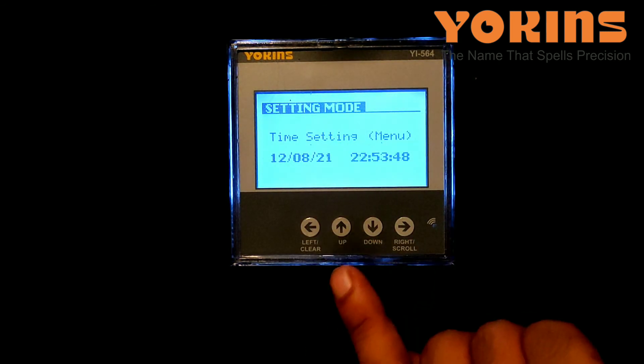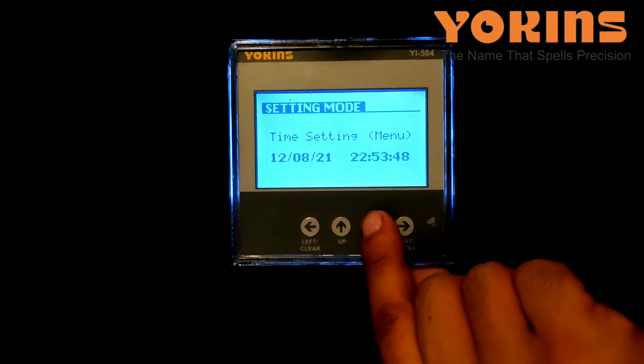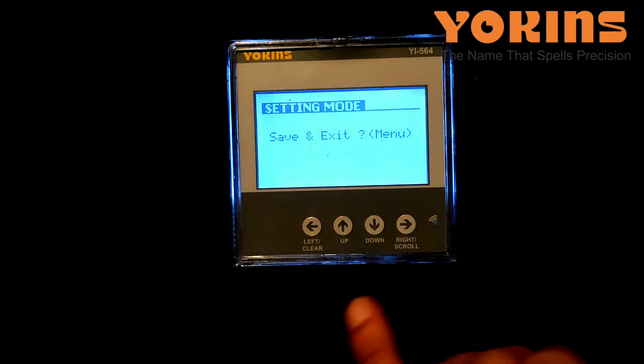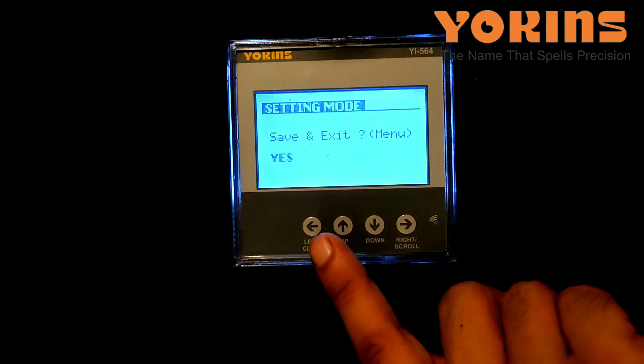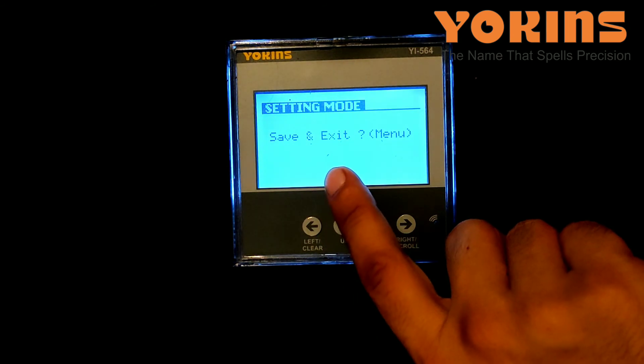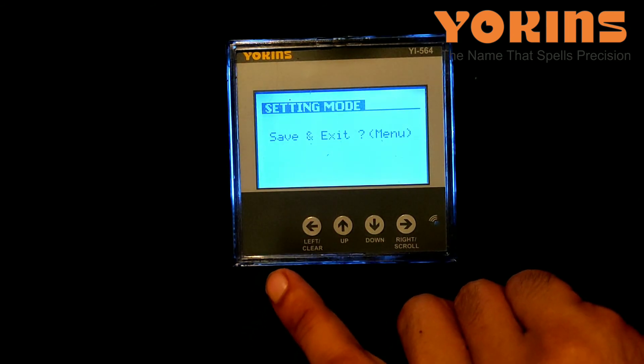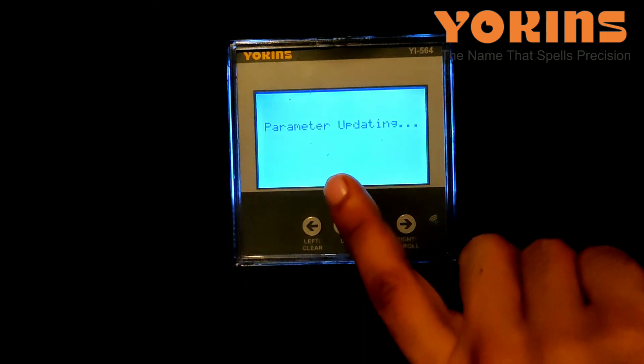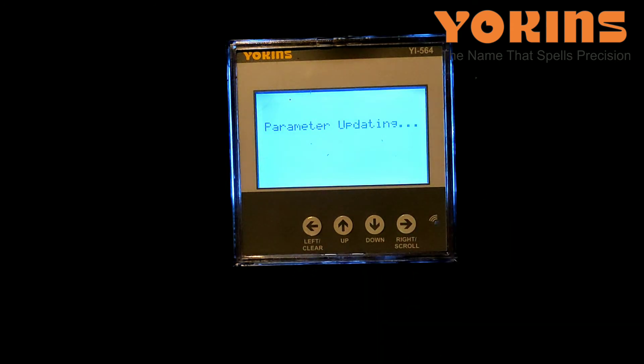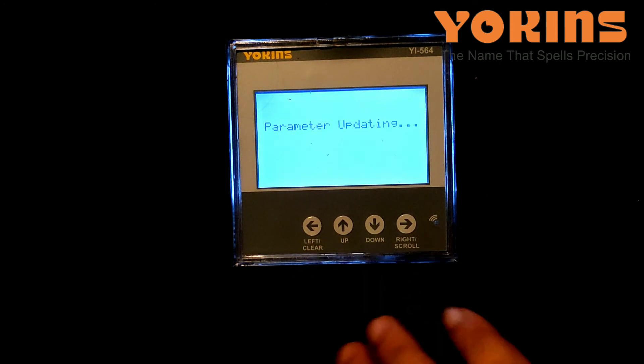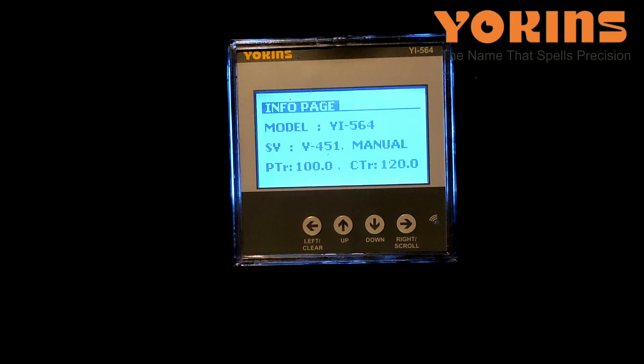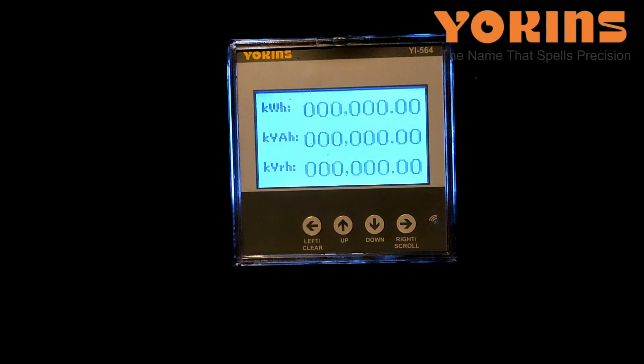Now it shows 'Save and Exit'. To save all the settings we have made, we'll press the right button. Make sure to save — if you don't, the settings will not be stored in this meter. By pressing right button, all settings are saved. We have now set a PT ratio of 11kV / 110V and a CT ratio of 600 / 5A in this meter. I hope you have understood — thank you.